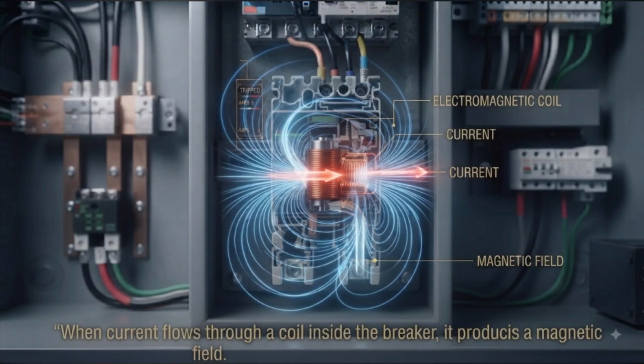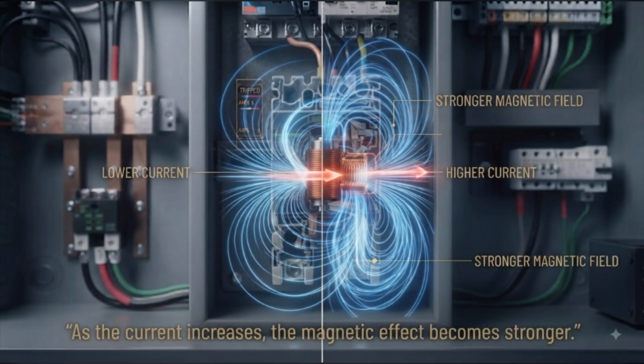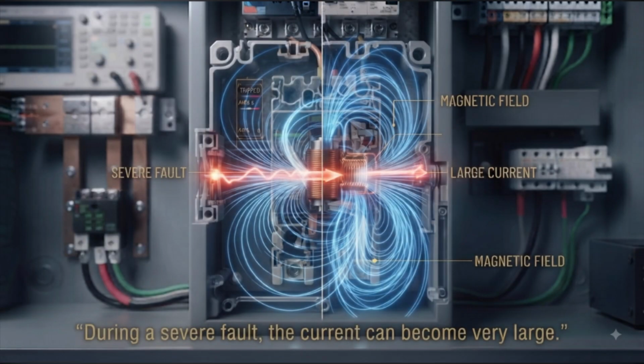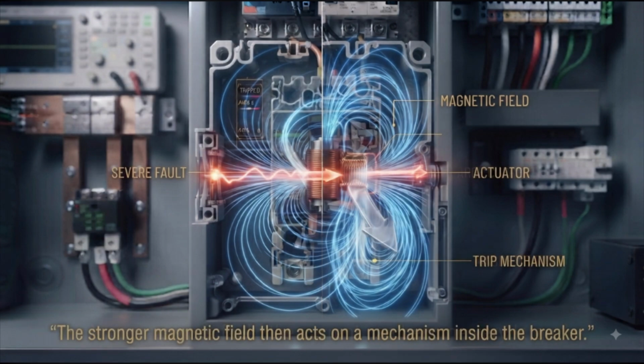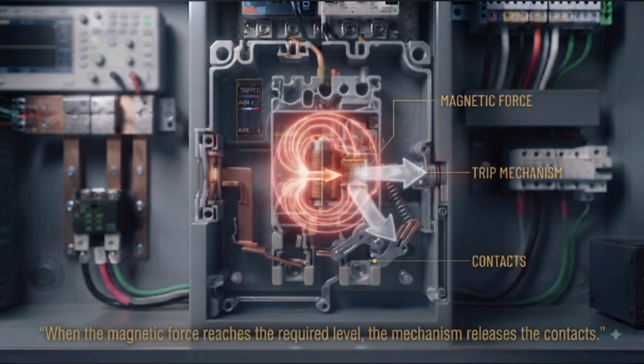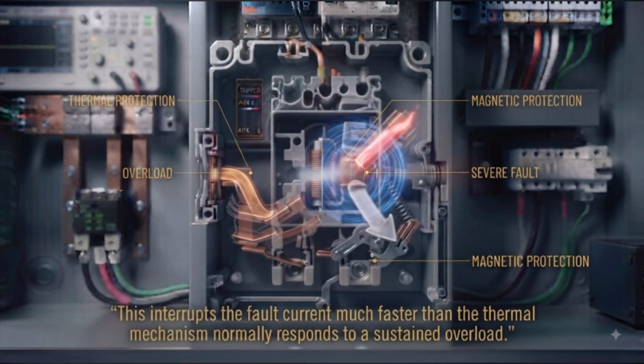The magnetic mechanism. The second major protection mechanism is electromagnetic. When current flows through a coil inside the breaker, it produces a magnetic field. As the current increases, the magnetic effect becomes stronger. During a severe fault, the current can become very large. The stronger magnetic field then acts on a mechanism inside the breaker. When the magnetic force reaches the required level, the mechanism releases the contacts. The contacts separate rapidly. This interrupts the fault current much faster than the thermal mechanism normally responds to a sustained overload.